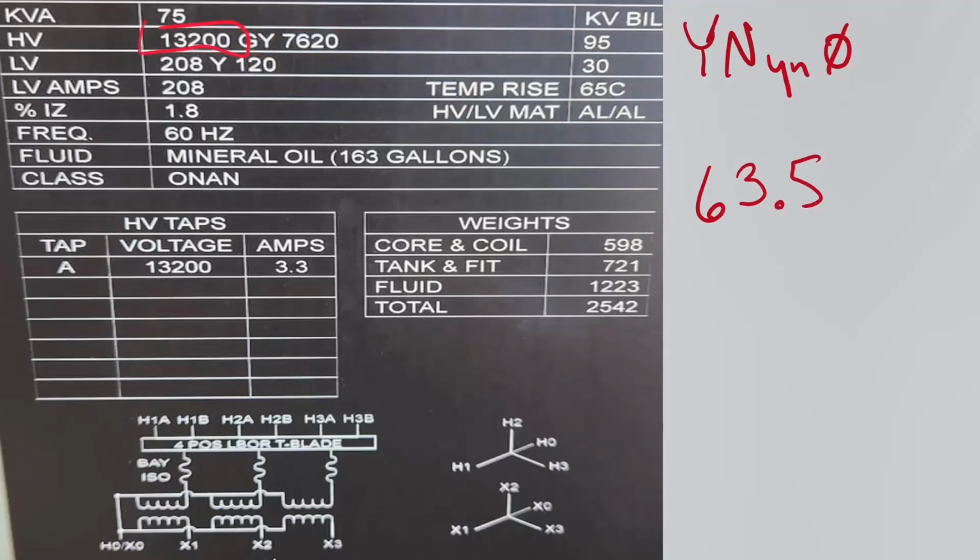Now, what I would never want to see anyone do is say, oh, I'm going to use my phase voltage, divide that by the square root of 3, use this, divided by the square root of 3. Well, what you're doing is 13,200 divided by 208, which, by the way, it's going to be the same number right here. And then you're also doing 1.73 and 1.73. The more you do with this, the more chance for error you introduce into it, okay?